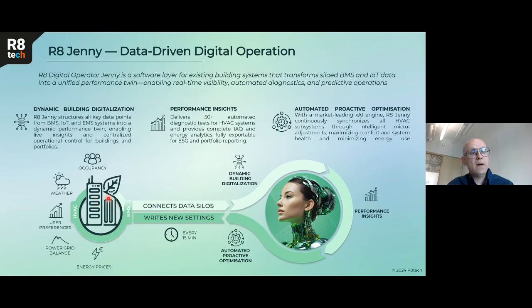So after we are taking all the necessary input data from the BMS, first while we start, we are adding our own category variable for all digital and analog input-output values for the BMS. It means for all the sensor values or the valve positions or the switches, and we are connecting them to our software. So it's partly automated, it's partly manual work. And after that, after the connection is made, basically we made a digital twin of the building.